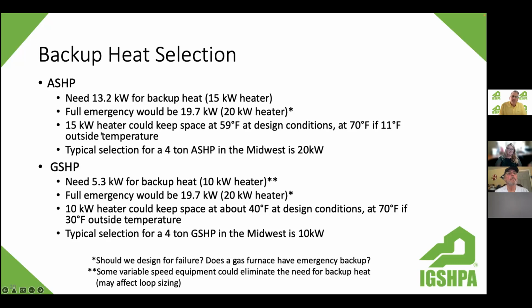If we did go with 15 on this air source heat pump, we would still be able to provide 59-degree temperature in the house, even at design conditions. What I've seen in the Midwest is most 4 ton air source heat pumps actually have a 20 kW heater, so I use that for my comparison. Really wouldn't have to have it, but it just depends on the comfort level with the contractor and the homeowner, in this case with a residential application.